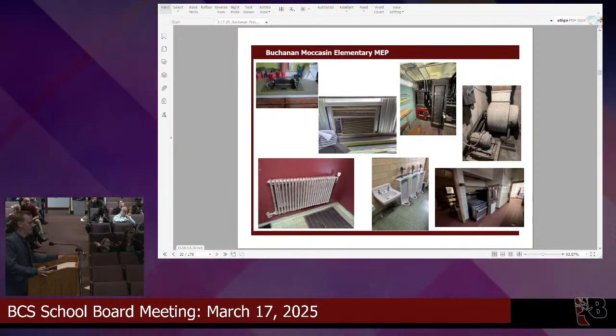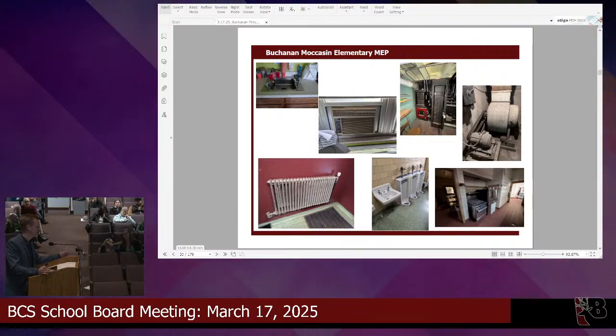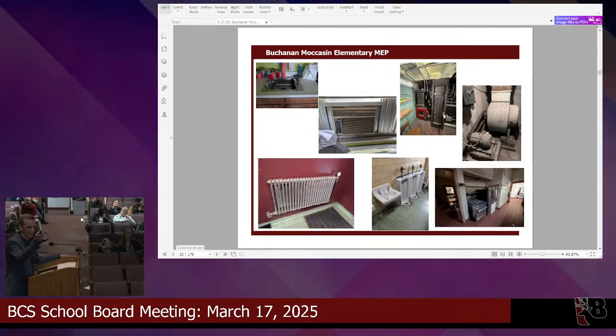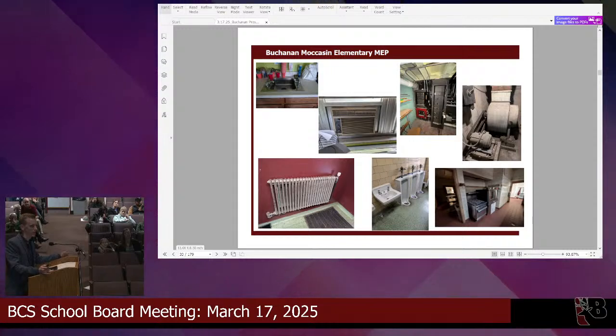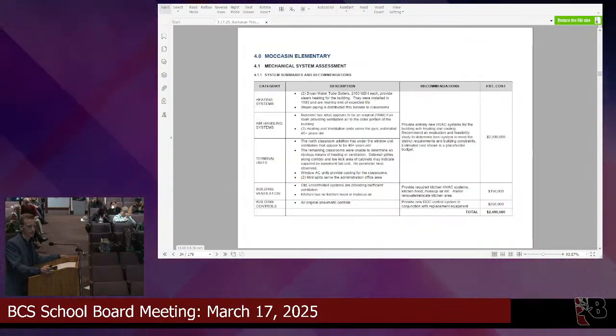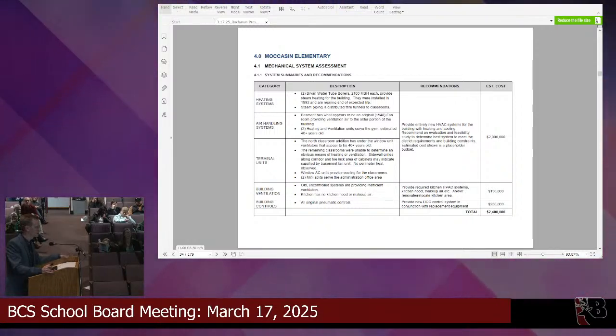Okay, so from an MEP standpoint for Moccasin, this one's kind of simple, where more or less all of the MEP is past its useful life. You'll see you've got some pictures here. On the far right, you've got a fan in the basement that does most of the ventilation. We've just got old heating systems that are past their useful life, and window air conditioners doing most of the cooling. You mentioned fire suppression in the kitchen, but there needs to be a kitchen hood first, really, to have fire suppression. So we're missing the kitchen hoods, things like that, would be important adds. I'm not going to go too deep, but I'm happy to answer questions as time goes on.